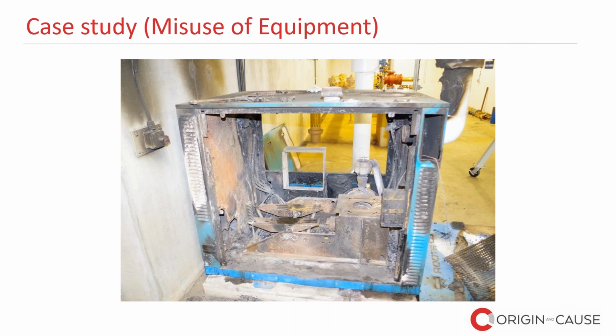So further information determined that we were informed that the 12-year-old blower had been operating, again, similar to the previous case, under a larger than normal load, as sewage had been rerouted to this blower to accommodate the failure of another. Maintenance had been completed recently, but it had been incorrectly done, and the combination of this and the above average sustained load resulted in the failure of the equipment. Again, we see that equipment should be operated as specified by the manufacturer. Get a thorough maintenance and usage record of the equipment. In our case, we actually had requested and received 12 years' worth, which was essential in determining the cause, which was related to the misuse.